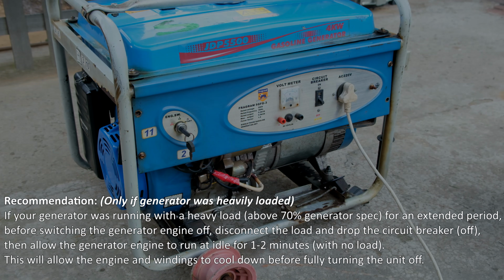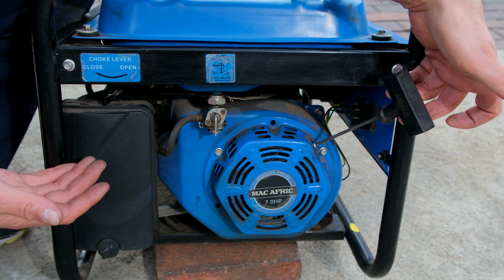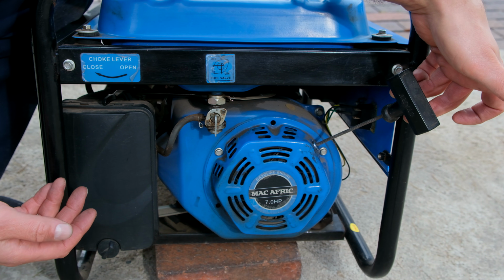If your generator has been running with a high load, say for example 75% of its maximum rated load, disconnect all the loads, let the generator get back to its normal idle and then let it run for about 2 minutes. This will cool down the engine without the load attached. You only need to do this step if the generator is running close to its maximum just prior to you switching it off.